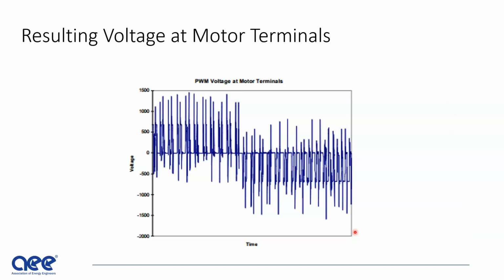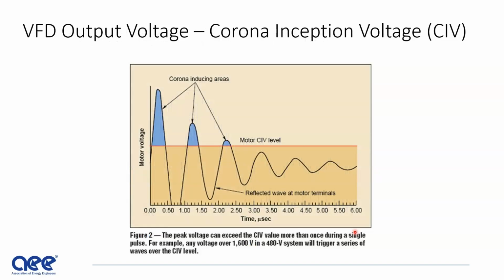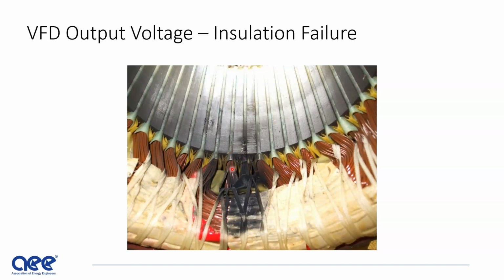Here's another way that the VFD pulses look at the terminal of the motor. You can see, in this case, a 480 volt motor, and we've got spikes, in this case, reaching up to 1600 or 1500 volts. This is where you get that punch through. The other issue you get is called corona inception voltage. So as you increase these voltage spikes on a motor, due to a reflective wave on the cable, you can get spikes that go above the corona inception voltage. And what happens is the insulation starts to ionize and creates carbon tracking for shorts. And this is a classic case of a VFD wound inverter grade motor where that punch through due to corona inception voltage actually occurred.